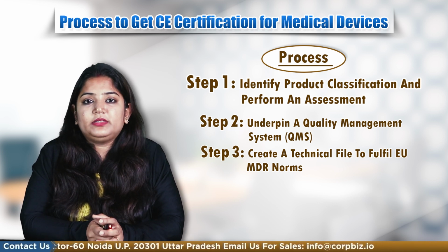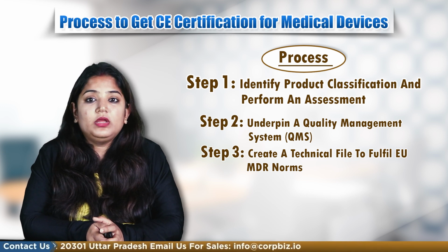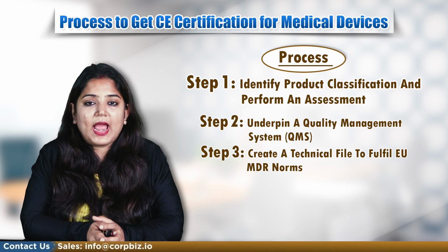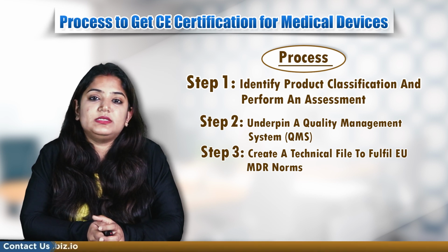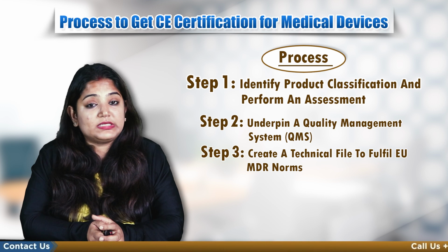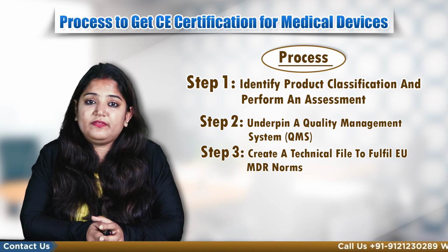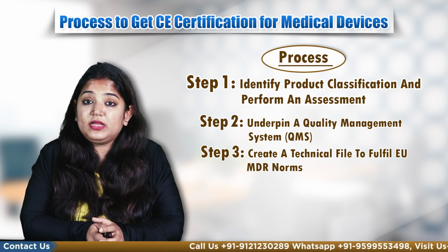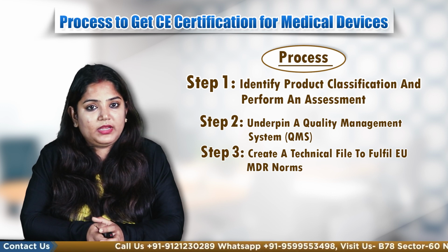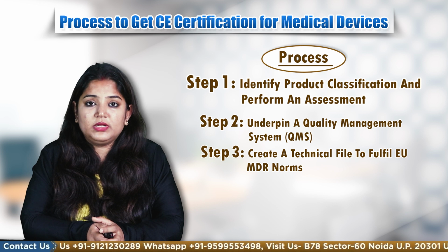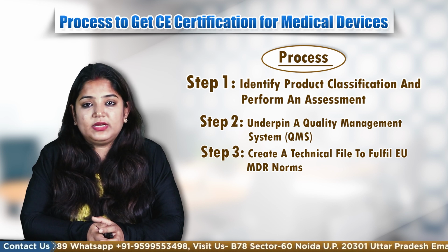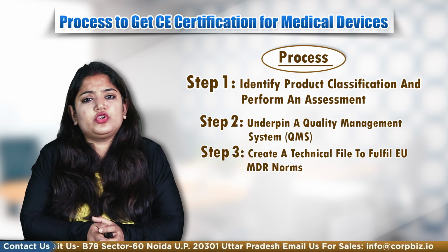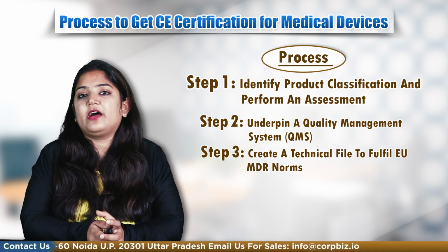In a nutshell, the technical file should enclose the following information without fail: product description and specification, details concerning manufacturing, risk management file, design verification report, validation test report, clinical evaluation, and labeling. The requisite information for devising and producing a technical file must be enclosed in your QMS. It should be within reach of concerned staff members.